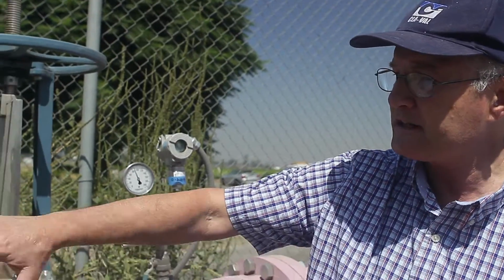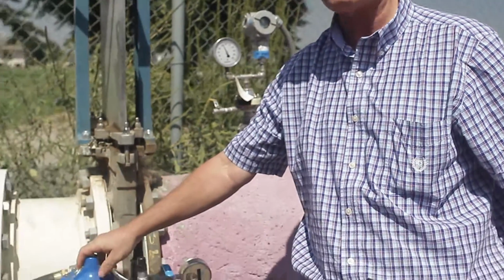I understand that the pressure drop across this valve is somewhere near 40 psi. Our engineering charts show that that output is close to 100 watts of power. The equipment they're powering here is far less than that, so we have lots of reserve. But this is our high power generator.